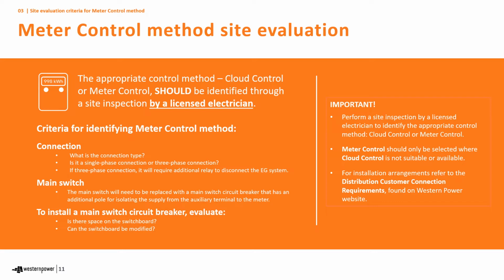What type of connection? As with all solar systems, the connection type is important. Is it a single-phase connection or a three-phase connection? For example, if it's a three-phase connection, it will require an additional relay to disconnect the EG system. This provides issues along the lines of space requirements for the switchboard, and rearrangement of circuits potentially to fit things in, and that's got to be considered. And similarly with these things, you need to add in a new main switch, which will control the source from the auxiliary terminal of the meter and provide isolation. So there's an additional pole on the main switch. So is there space? Can you modify the switchboard without extensive cost?